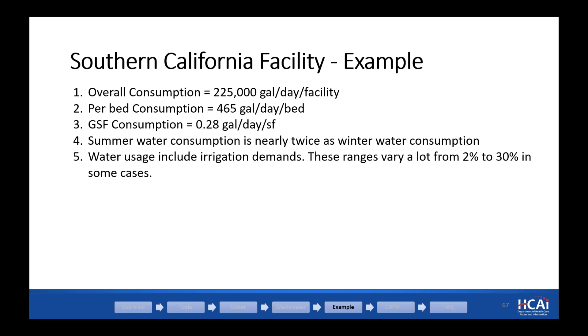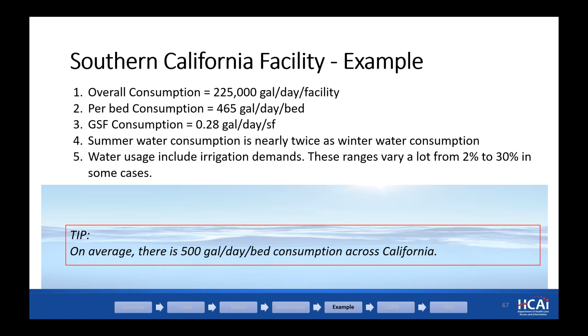So that is a lot of water. On average, there is a 500 gallons per day per bed consumption across the hospitals in California. Again, hospitals need water for their functioning. If you see that 500 gallons per day per bed, the code required minimum is 50 gallons per day per bed. So that's 10% of what hospitals typically use on a daily basis per bed. That's why minimum might not be the answer. That's why we are asking for a water rationing plan, where things are thought through and the actual usage is calculated based on the emergency protocols.